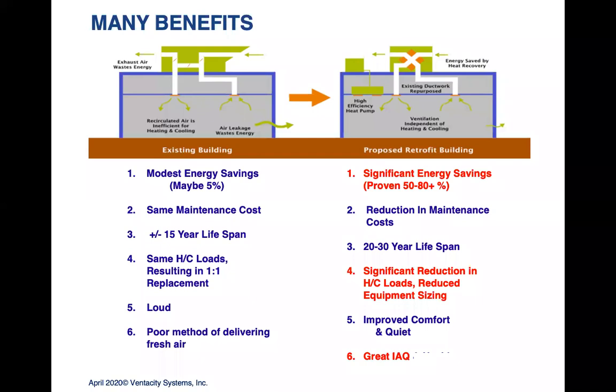If you take 9 4-ton RTUs off the roof, you're going to replace it with 9 4-ton RTUs. So you're not going to change the load at all when you just replace. The model that we have presenting today has significant energy savings, and I'm showing there 50 to 80% plus, and we have achieved that significantly with all the projects we've done.